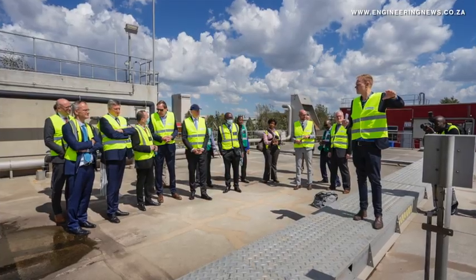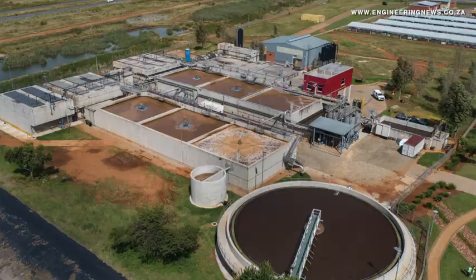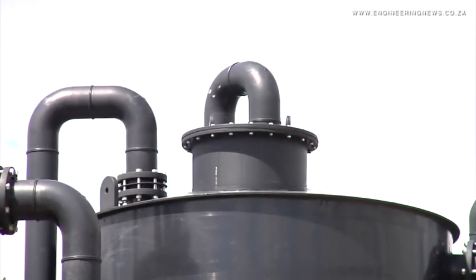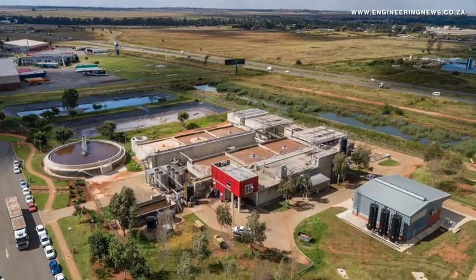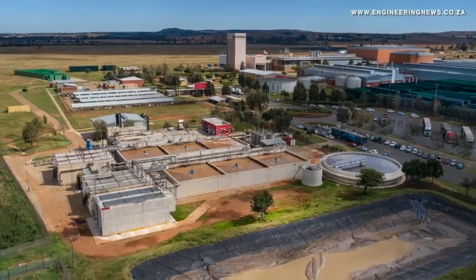Total capacity of the effluent treatment plant is around 7,000, so that's 7,000 cubic meters a day, that's 7 million liters. And out of that, around 30-40% is sent to the recovery unit, and the recovery unit is then producing 45 million liters a month, and that's more or less the equivalent of 18 Olympic swimming pools that the brewery is saving that way. Water that they normally need to offtake from groundwater, they are now saving by the water reclamation plant.